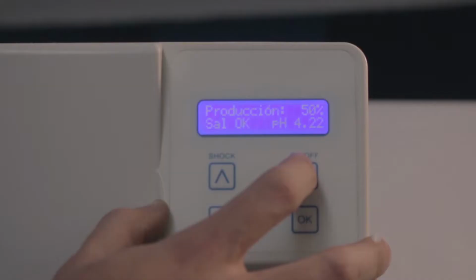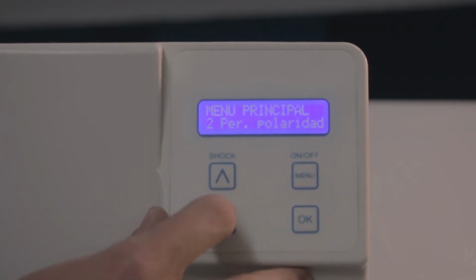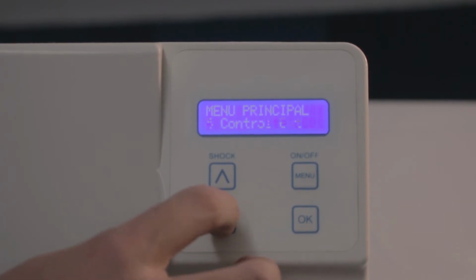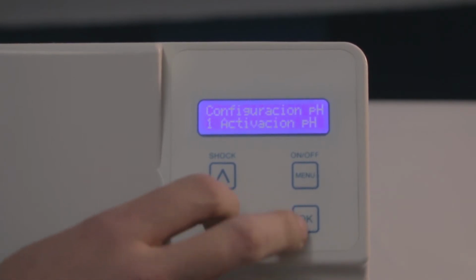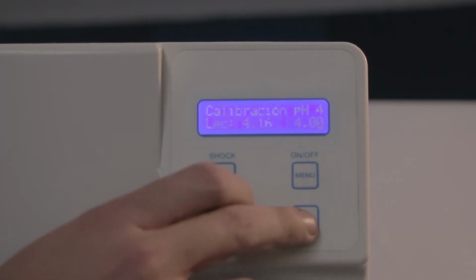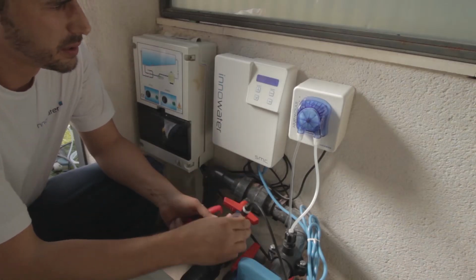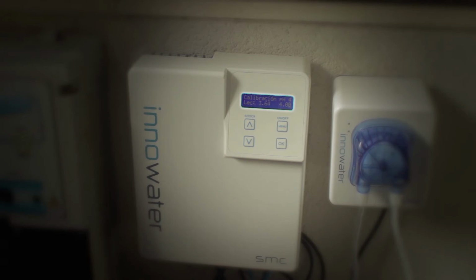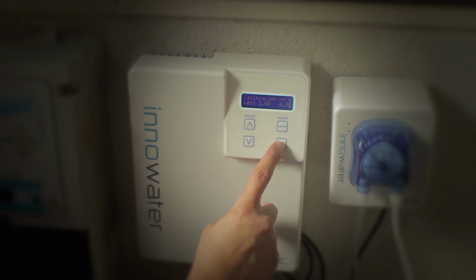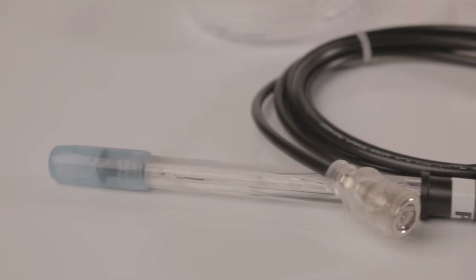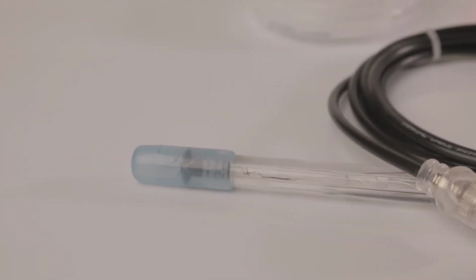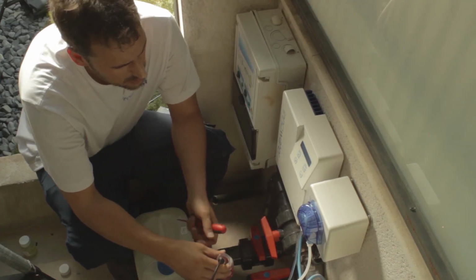Step 5. Calibration. To calibrate, go to the menu to point 6, pH settings. Then, in this menu, go to calibration pH 4. Take the pH 4 liquid and pour it into the probe. Wait until the calibration is stable and then click on OK. Clean the probe head with water and dry it with a cloth to avoid contaminating the calibration product.